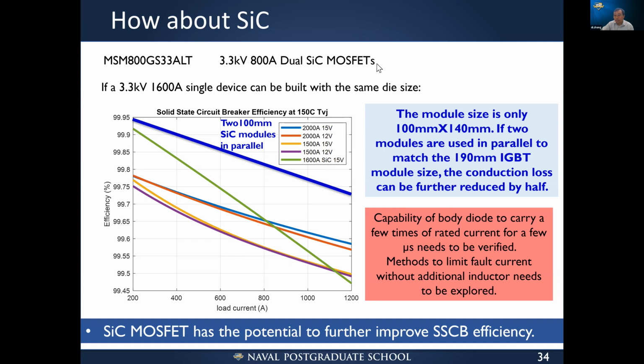That may work for converter applications because we know the dead time can be controlled to be less than 1 microsecond. However, for breaker applications, the current may be very high, and the capability of the body diode to carry a few times the rated current for a few microseconds definitely needs to be verified. The reason is that IGBT doesn't have a body diode, right?